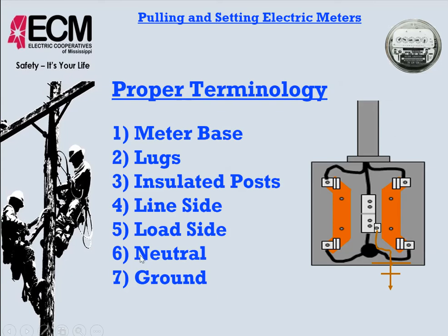And then also the neutral lugs, which are typically here in the center, but not always. Sometimes they're to the side. There are a lot of different configurations of meter bases, but definitely they will have a neutral lug that our line side neutral will hook to the load side neutral. And then also the grounding lug. Typically, best place for it is here with the neutral, so that we're making sure that we're grounding that. And then also we'll have a piece of wire that goes from that and then goes down to our ground rod.